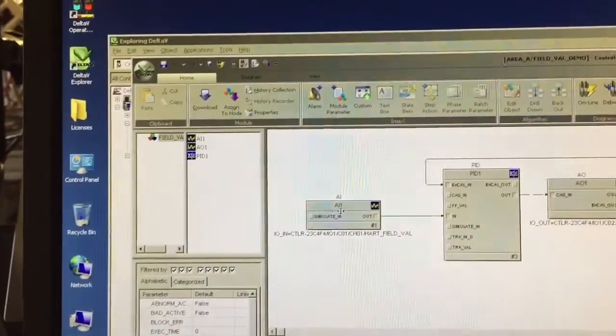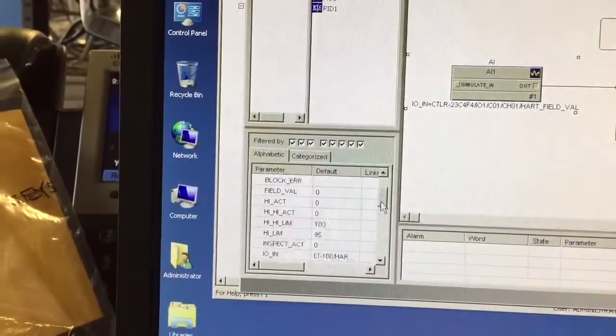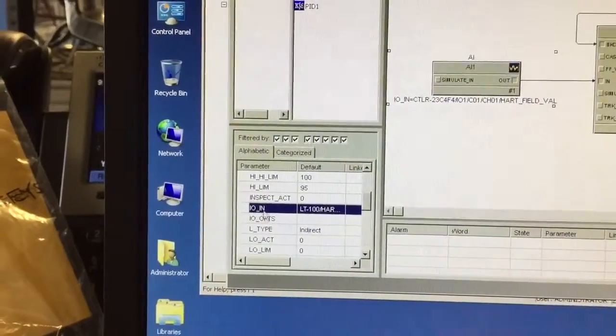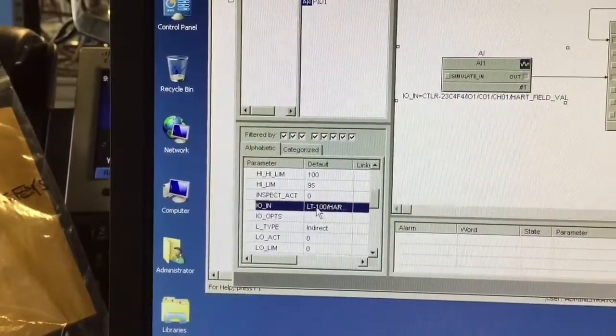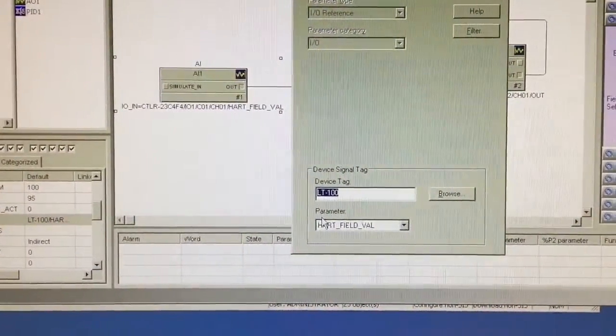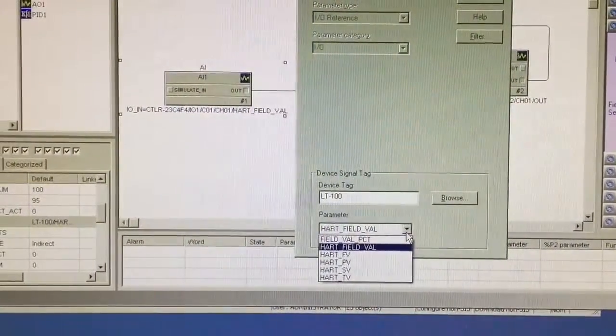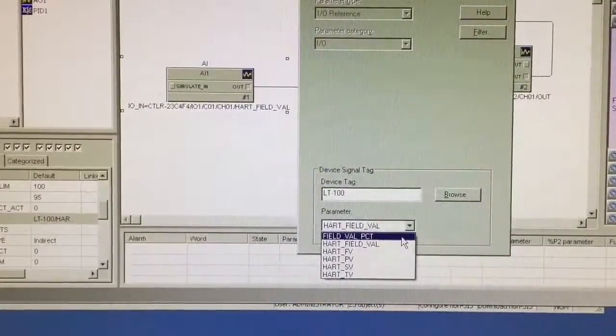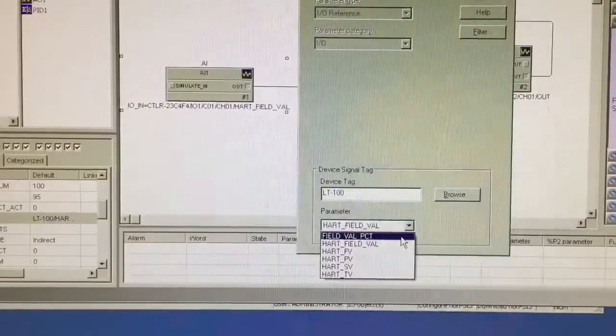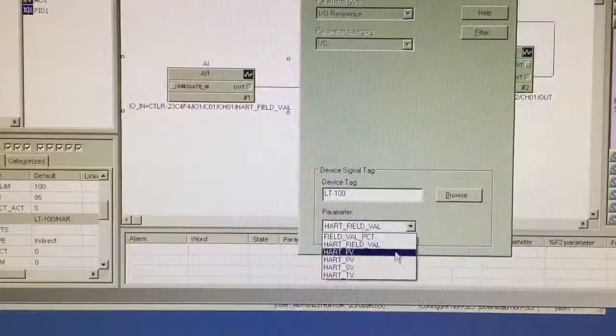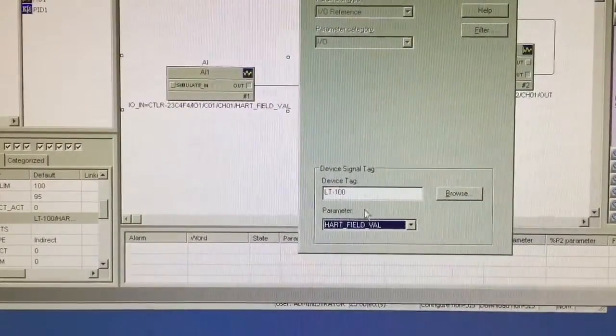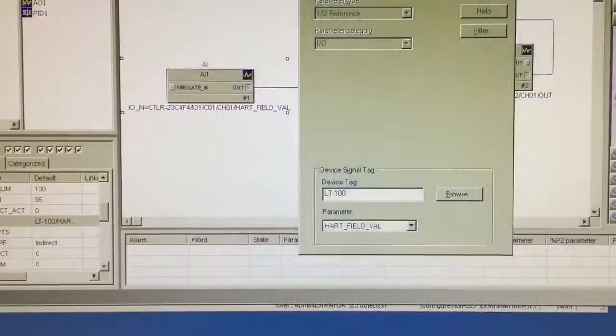And then in control studio, when you're working with your AI block here, your analog input block, you need to ensure when you're linking it to the device on channel 1 that we just set up, we've named it LT100. When we double click on this, the IO_IN parameter, you can see right here, this is where you select HART_FIELD_VAL. If you do not have a HART enabled device, you will only be able to select FIELD_VAL_PCT. That'll convert the 4 to 20 milliamp value to a 0 to 100% value. By selecting HART_FIELD_VAL or any of these HART parameters, we can now write values out to the device.